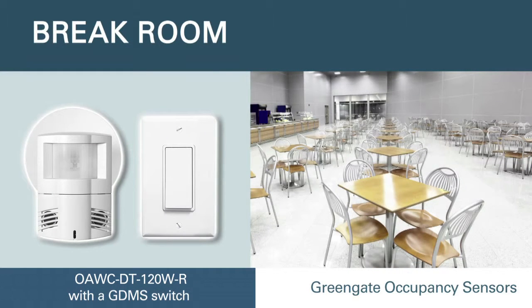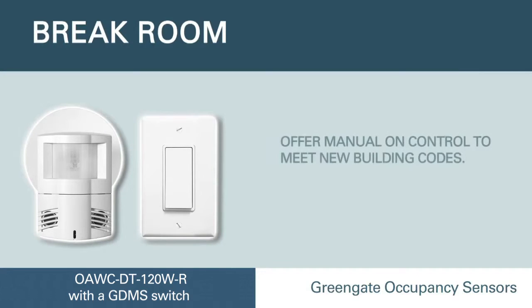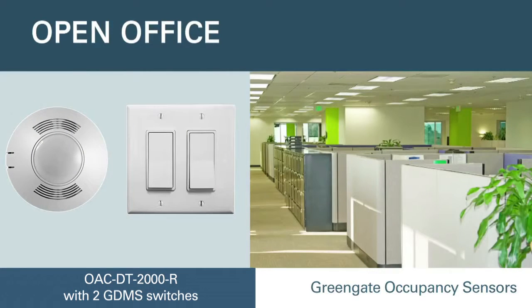In the classroom, you can combine the Greengate wall corner-mount sensor with the wall switch to provide the manual on, automatic off control now required by many codes.